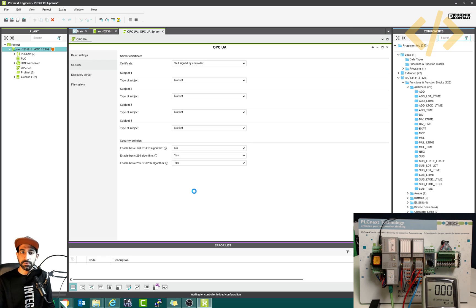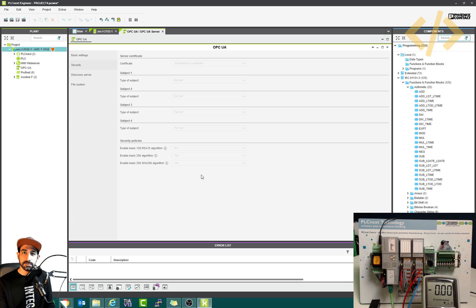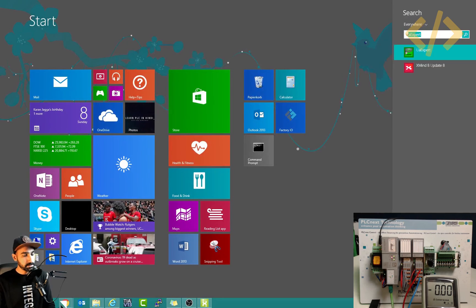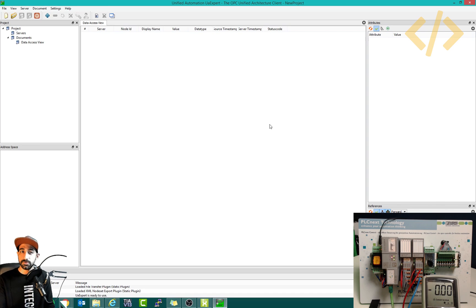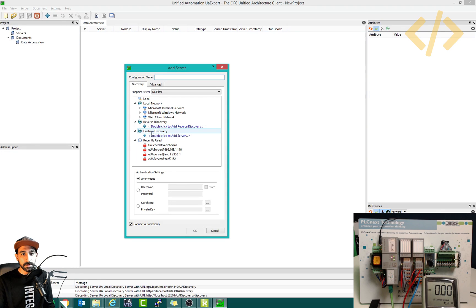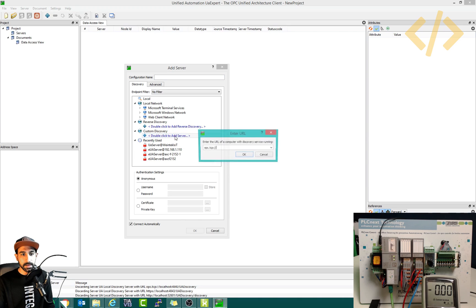Now we will open the OPC UA client. The client will extract the values of these tags from the OPC UA server — that's the idea. The client can be any third-party software. I'm using one called UA Expert. These third-party tools take values from the PLC and you can develop other applications using these variables, which is quite beneficial for IoT work. In the client, I will add a server by going to custom discovery and double-clicking to add it.